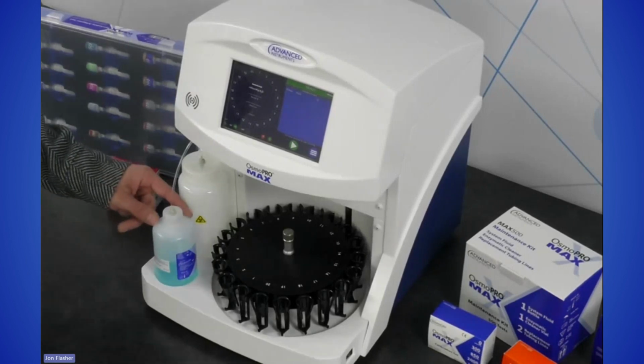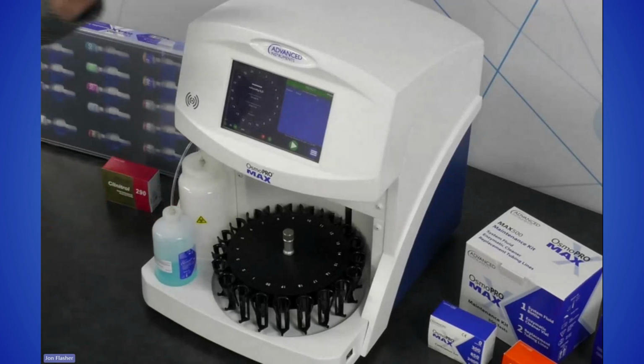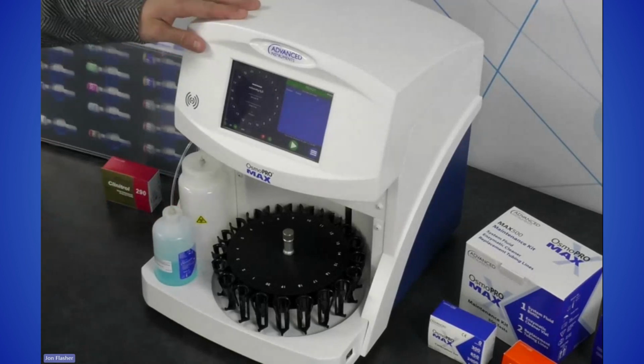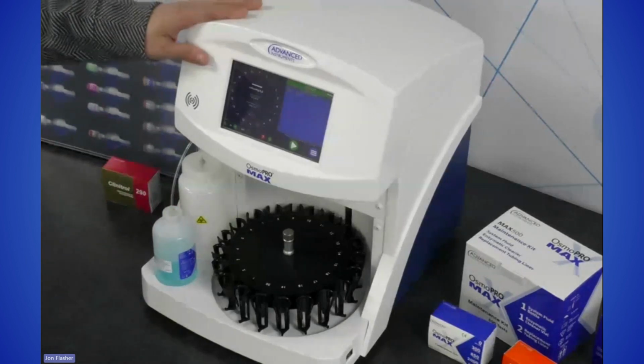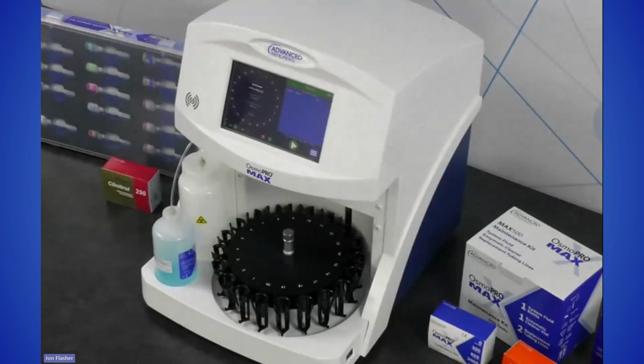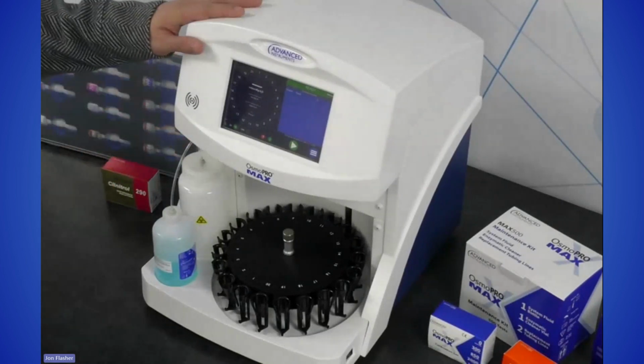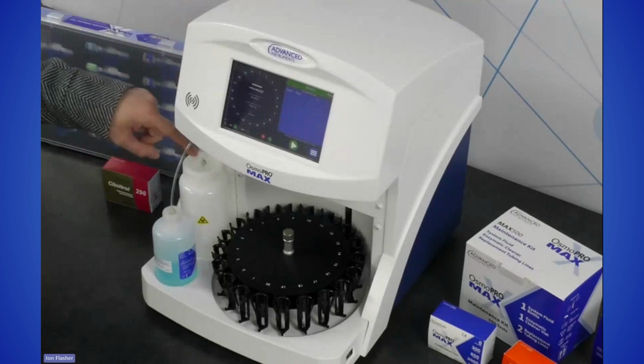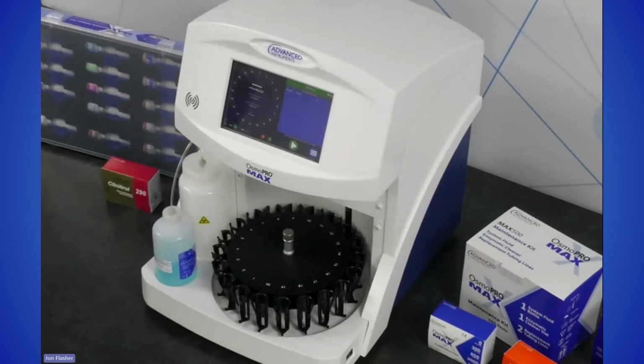Here you'll see the system fluid. The system fluid is what's used to make sure the fluidic pathway, because this is a flow-through instrument, stays clean in between tests, in between samples. So that's what that's used for. And then all that system fluid has to go somewhere. So it goes right here in the waste bottle, which lives behind the system fluid.